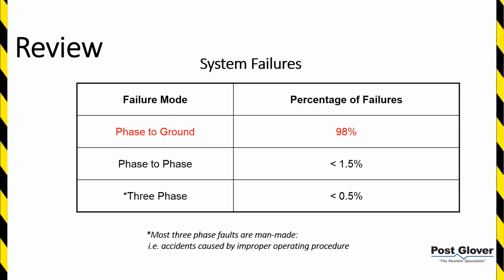So phase to phase, we're talking about a phase to ground fault that has degraded, caught a second phase to ground, and then we now have a phase to phase. That's usually how it happens, although it's possible to start off as a phase to phase. And then three phase is very rare. It's usually somebody made a pretty good mistake, typically.